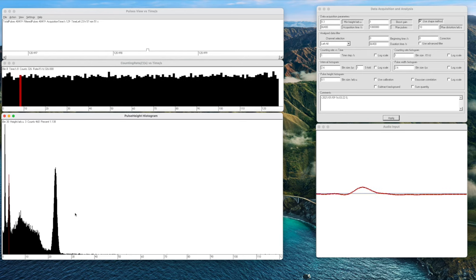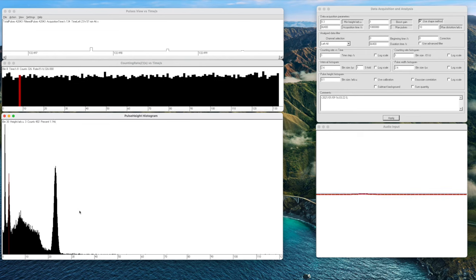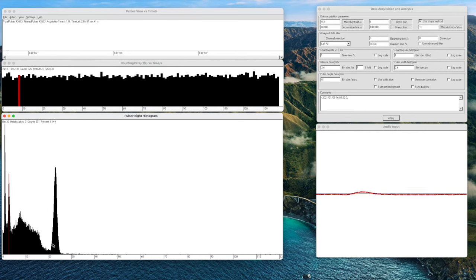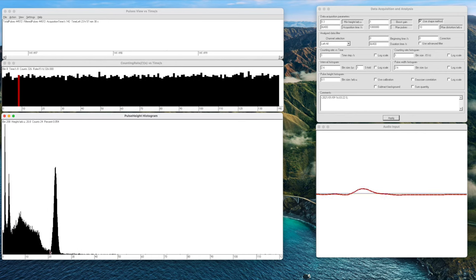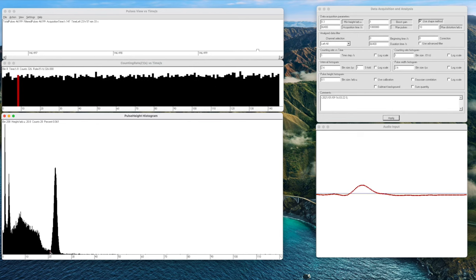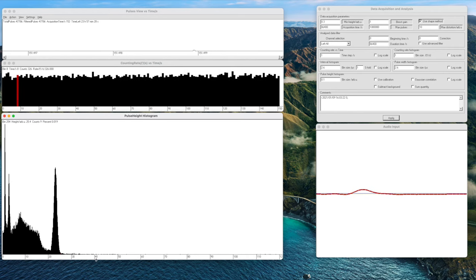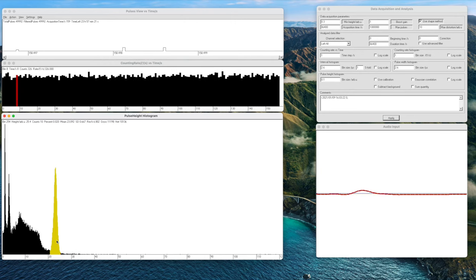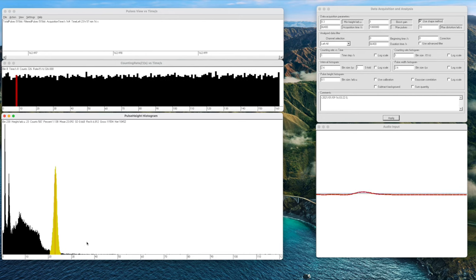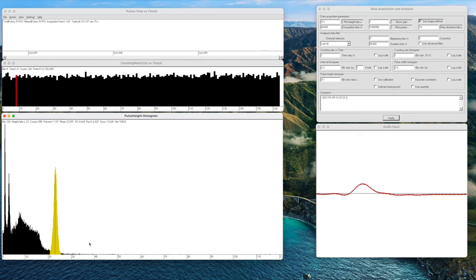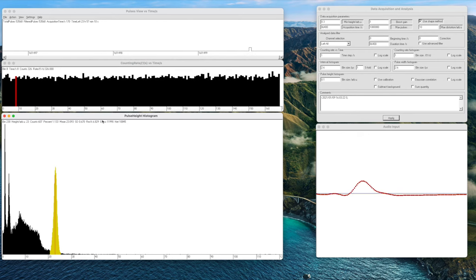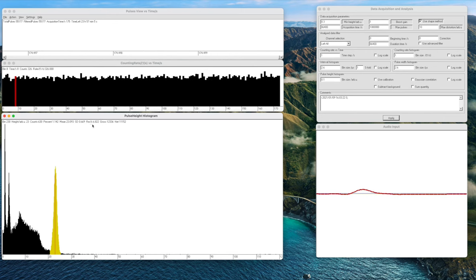When we do gamma spectrometry we want to know what's happening in a particular region of interest. We can select our region of interest with PRA simply by clicking on a bin to the left of our peak and pressing the B on our keyboard. Then we select the bin at the end of our peak and press E for end. We have now selected the region of interest and it will highlight itself in yellow. When we click anywhere inside the region of interest we will get some extra information up here such as the resolution of the detector here which is 6.8 percent in this case and it also gives you the net counts in the region.